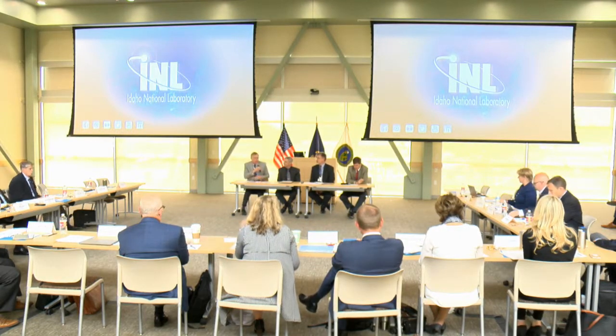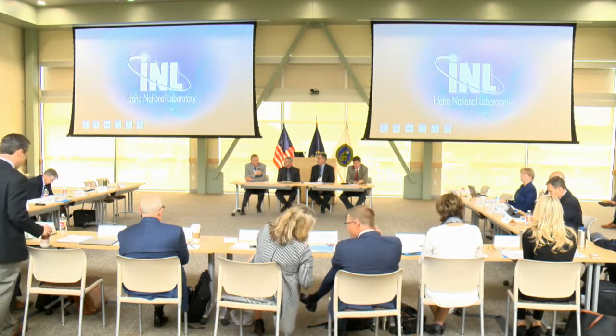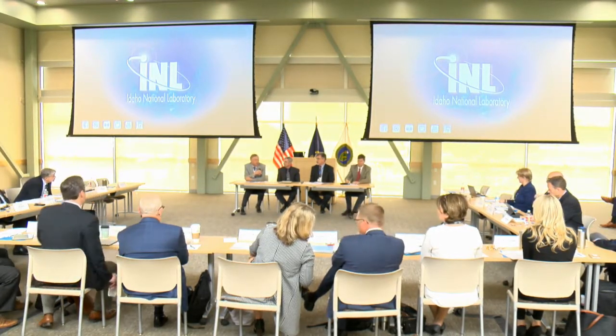Paul, thanks for the question. Certainly water is an important consideration. For this particular plant, we don't anticipate using water in any of the major processes for heat removal. Because sodium is the coolant, we don't use water as a coolant, so there's not a throughput of water from that standpoint. When it comes to cooling the reactor on the secondary system, it's not necessary to have a cooling tower where you essentially spray water through it either. The way that we remove the heat from the reactor is a direct exchange from the sodium secondary through essentially radiators to the atmosphere. And so it's very low water usage. As a matter of fact, potable water usage, things like that, will really be the primary use of water in this facility.